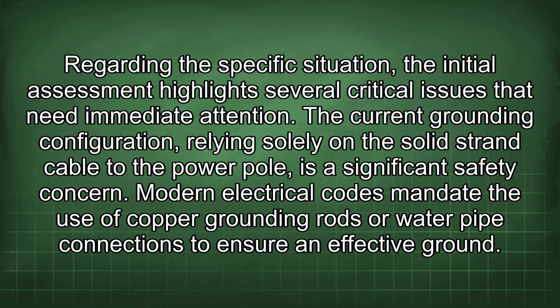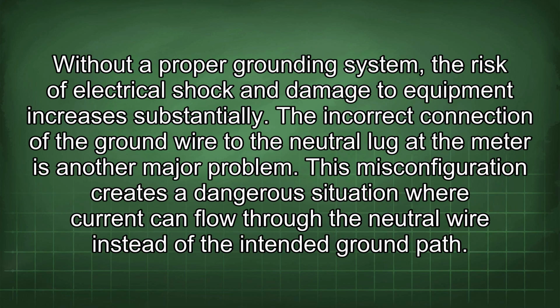Regarding the specific situation, the initial assessment highlights several critical issues that need immediate attention. The current grounding configuration, relying solely on the solid strand cable to the power pole, is a significant safety concern. Modern electrical codes mandate the use of copper grounding rods or water pipe connections to ensure an effective ground. Without a proper grounding system, the risk of electrical shock and damage to equipment increases substantially.